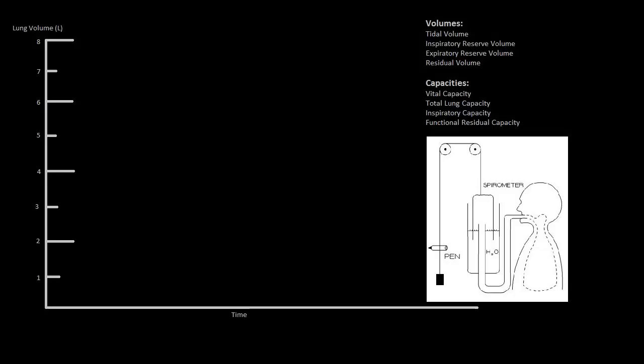Because as the name implies, we're able to assess pretty well how the lungs are functioning. The spirometer itself is a gas enclosure, and the gas is surrounded by two bowls — one on top and one on the side. Between the two bowls we have some water to seal this gas enclosure, and this gas enclosure is connected to the patient's lungs through a long tube. This tube is sealed at the mouth so that no other air can enter, and when the patient inhales, the gas is taken out of the enclosed chamber, through the tube, and into the lungs.